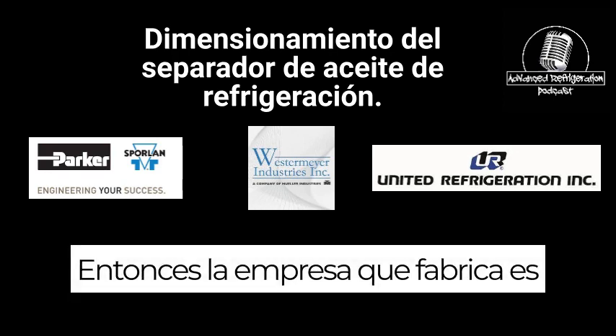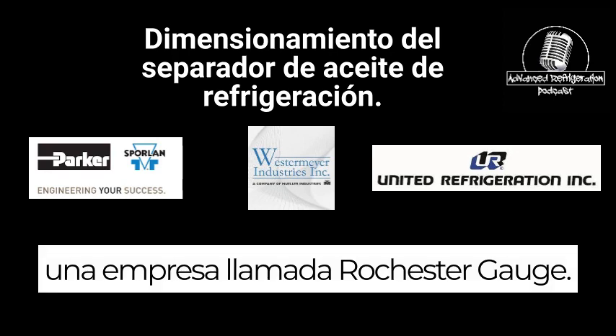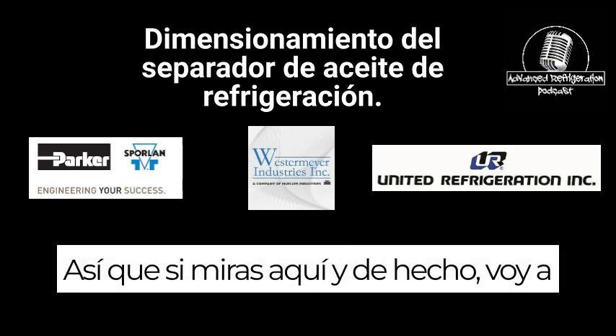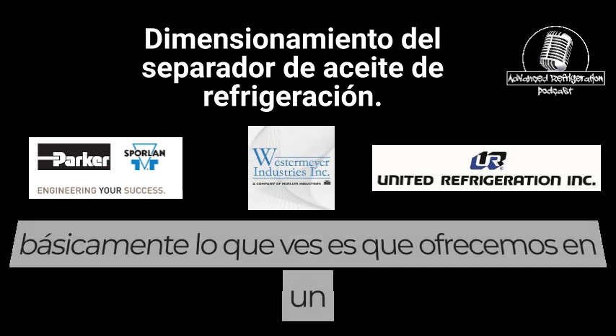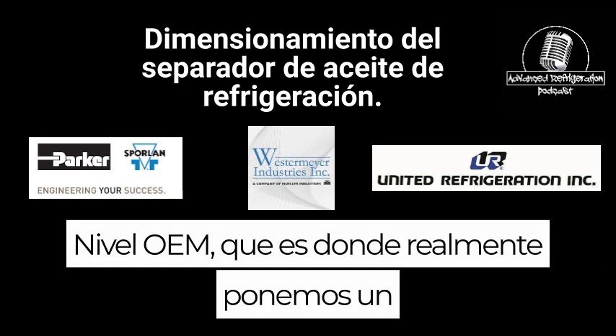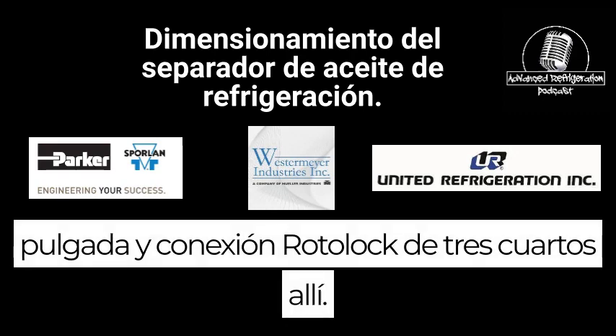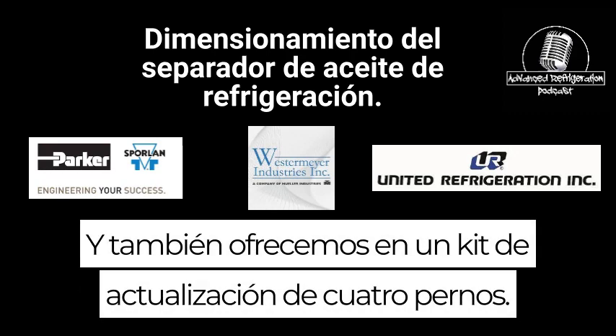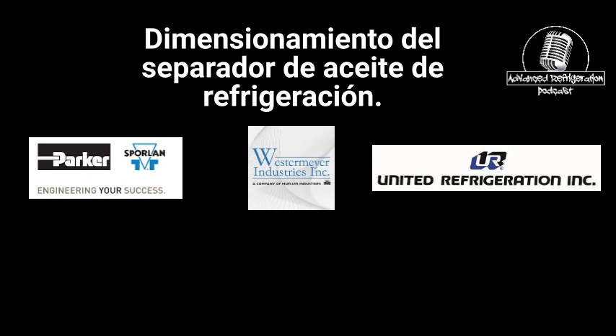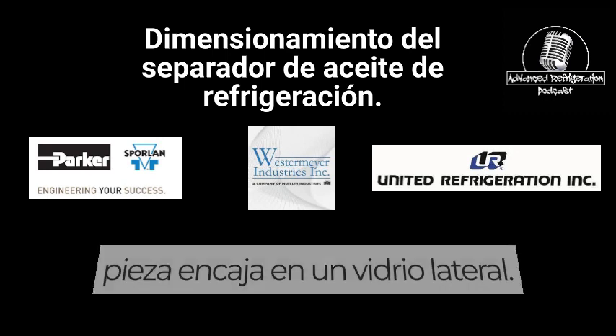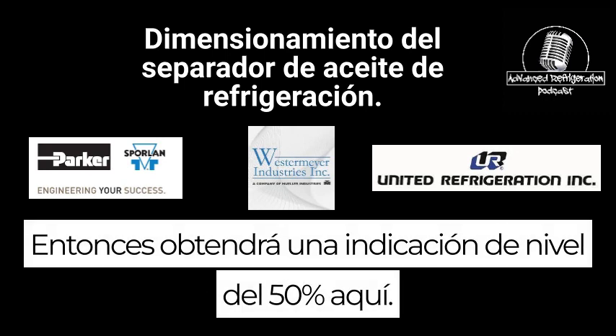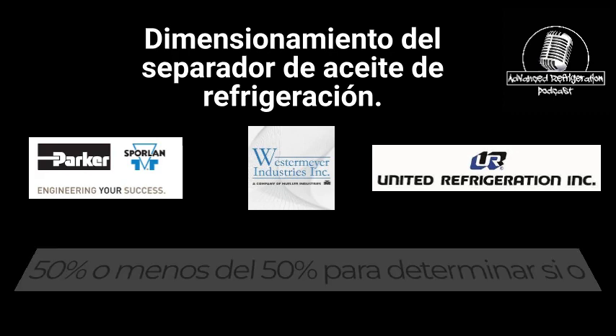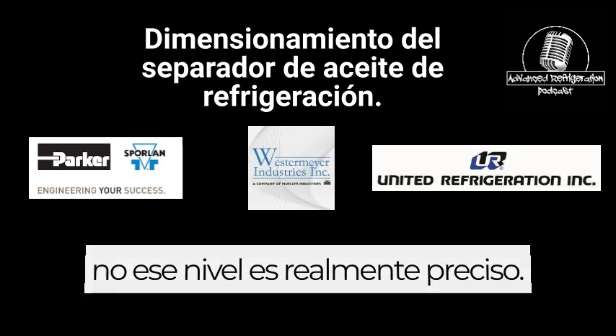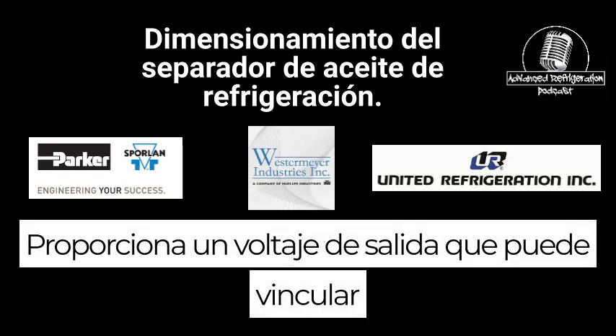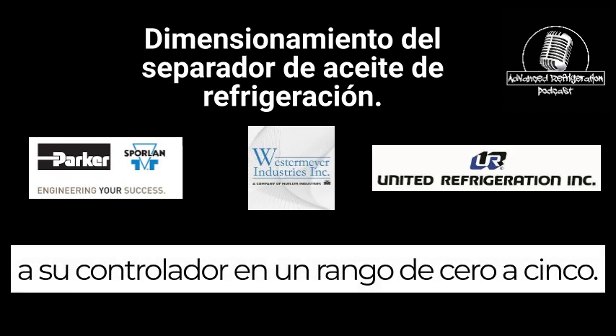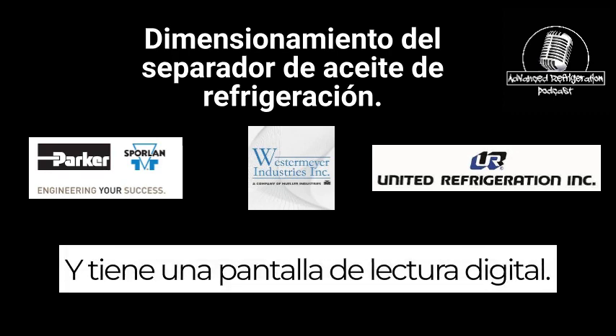The company that manufactures it is called Rochester Gauge. I'll pull up another sheet here in a second, but basically we offer this in an OEM level, where we put a 1 3/4 Rotolock connection on there, and we also offer it in a 4-bolt retrofit kit. This is actually a sight glass, and this electronic piece snaps onto it. You'll get 50% level indication, so you'll at least know whether you're above or below 50% to determine whether that level is accurate. It provides an output voltage you can tie back to your controller at a 0 to 5 range, and it's got a digital readout display.